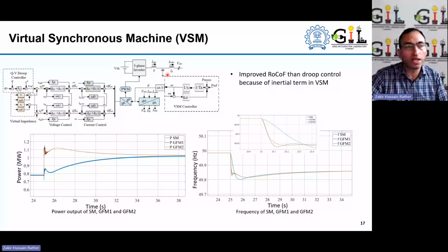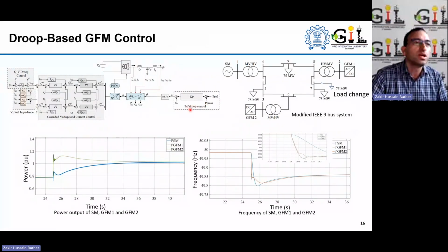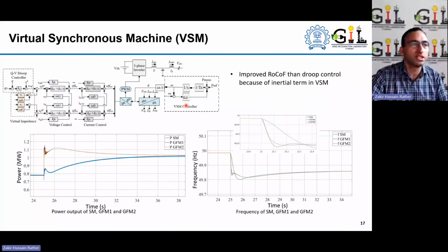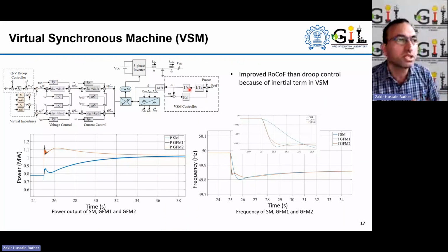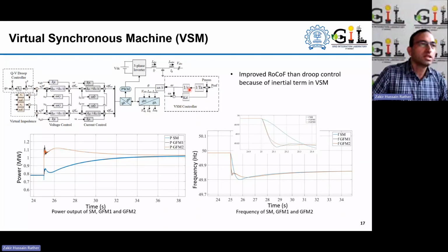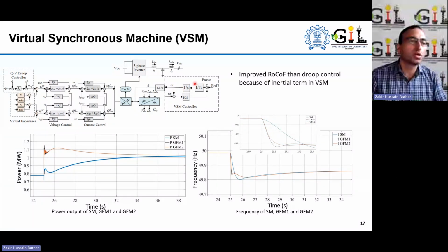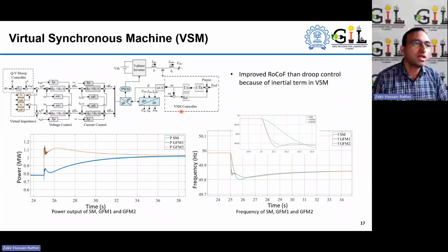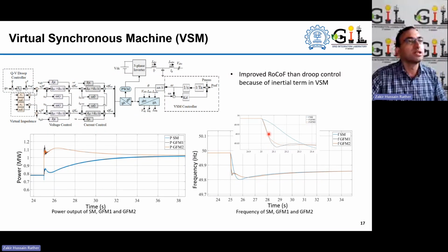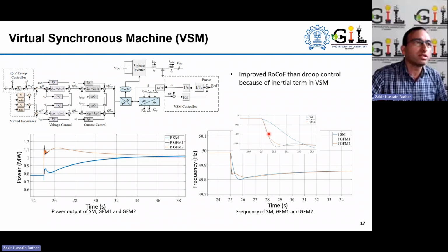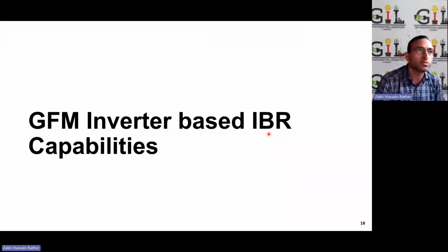Similarly, for the virtual synchronous machine, the difference here is that it provides this P-f droop control based on the frequency change, and it accordingly changes the power. Here, the swing equation that we have in the dynamics of the conventional synchronous machine is being introduced in the overall control. That's why it's named virtual synchronous machine. Similar cases here, you can see the response. Again, a similar output, but the RoCoF here is relatively better in the grid forming case compared to the previous droop-based control topology. There are others also. Again, these are sample cases that we show for the capabilities and responses of these different converter control topologies for the grid forming inverter.